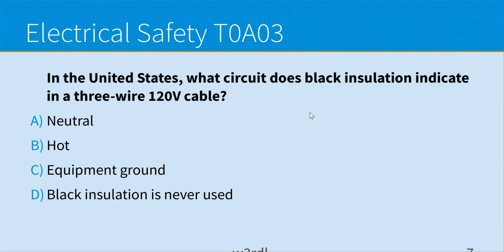It's kind of confusing, because it's not the same as for an electronics technician. Right. Yes, we normally use black for ground, or for zero potential. In AC or power distribution, the black or the red insulation indicates the hot lead, and the white or off-white, called neutral, is the neutral. And then usually green represents the safety ground.